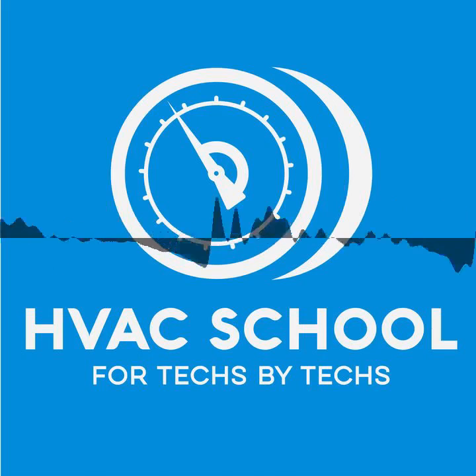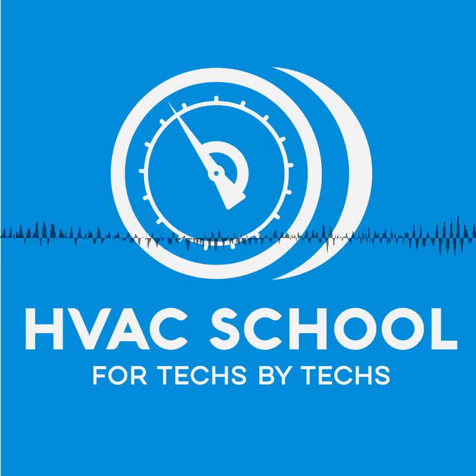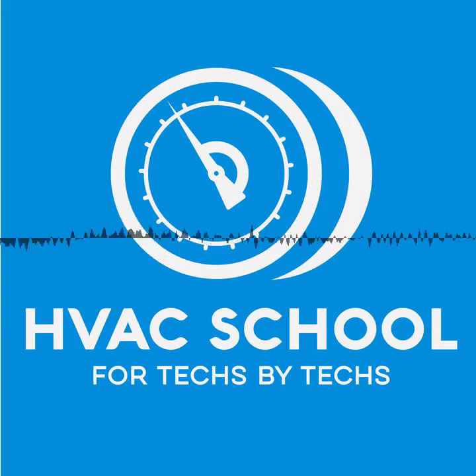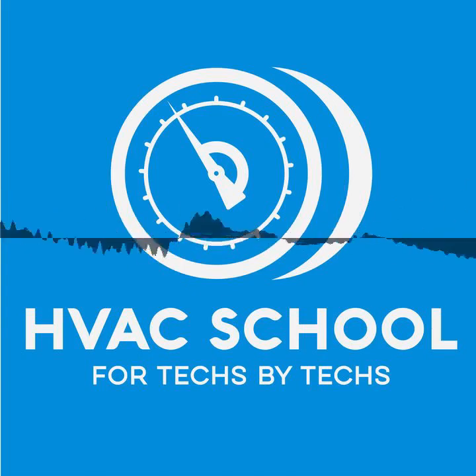So when you have a compressor burnout, the first thing you need to do is follow all the proper procedures: performing flushes, using suction and liquid line dryers of the proper type and size.